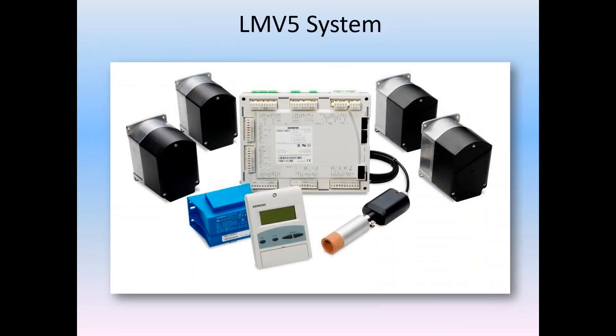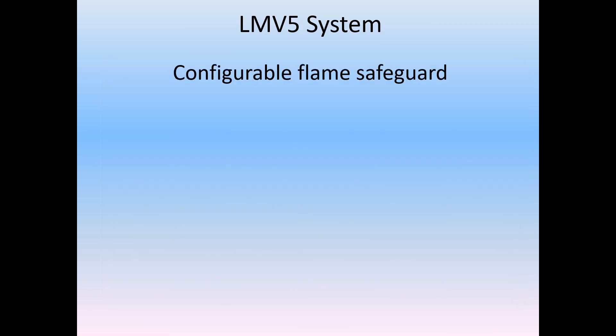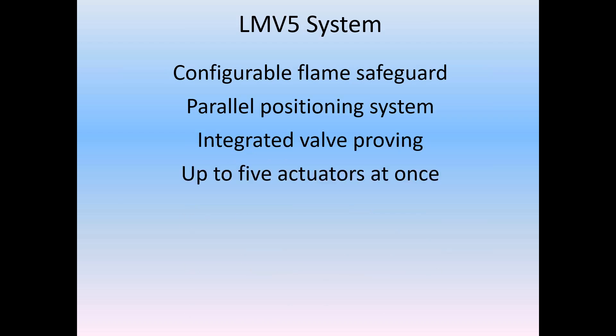The LMV-5 system shown here, primary features include a very configurable flame safeguard, a parallel positioning system for fuel and air ratio control, integrated valve proving, up to five actuators at once, internal PID controller, as well as optional O2 trim and variable frequency drive.